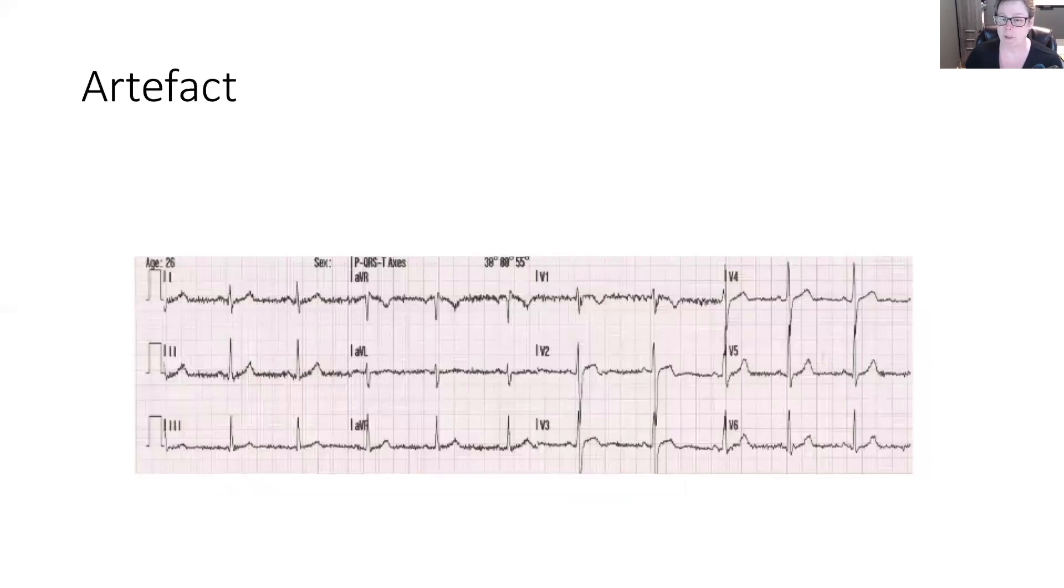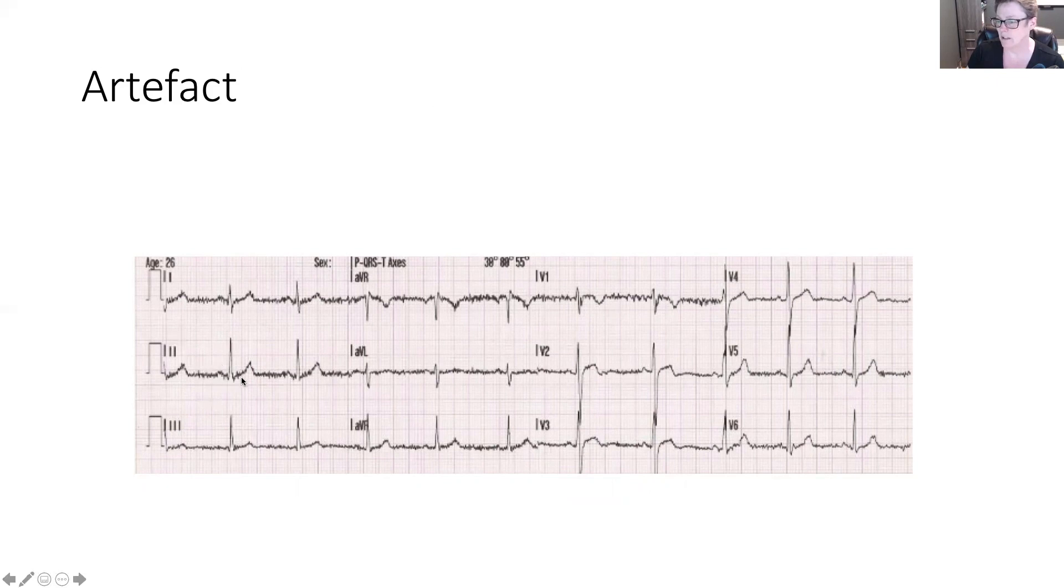Artifact happens when people are moving. Maybe they're shivering or they're tapping their foot. But then we can get this little vibration happening in the waveform. We're looking at line two or lead two. We see this vibration. It's really hard to identify some of the particular features. And that can cause a little bit of a challenge.